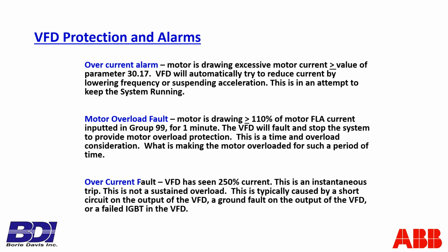In that case, during that acceleration, the drive will simply stop accelerating and hover like a helicopter taking off. It goes to a certain height and says, oh, we've got a little issue here. Let's sit right here and see if we can get this rotor to catch up to the stator. That should cause the current to go down, and we should be able to continue on our acceleration. So this is an alarm that tries to keep us running and the system online through a little bit of a transient event.